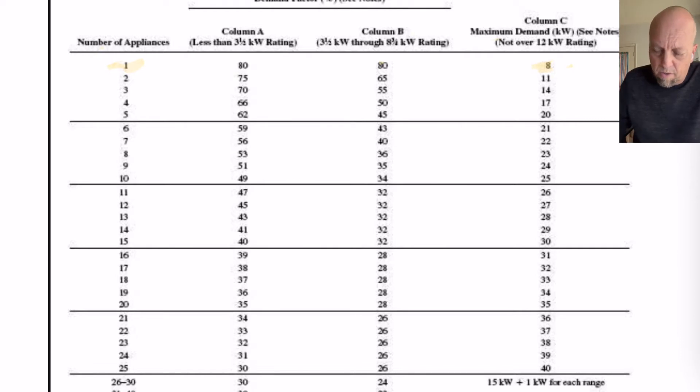Also, if you were to look in columns A and B, take a look at those. Those are your demand factors. So, that means those are multipliers that you will have to use to figure out your loads for those smaller ranges. But column C is already figured out for you. That is the load itself. They've already done all the math for you.